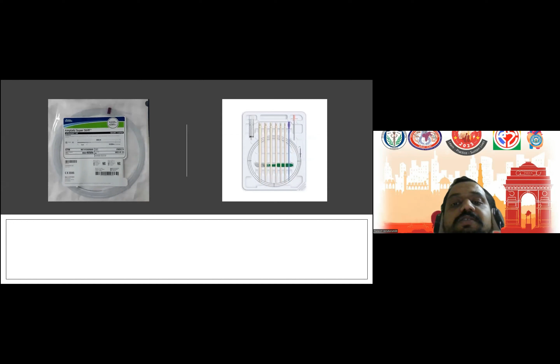Along with that, a multi-parameter monitor for the patient and one monitor for your circuit also, if you are measuring the pre-pump and the pre and post oxygenator P2 and P3 pressures. Because the machine does not have inbuilt P2 and P3 monitoring, you need an extra monitor for that. So these are the machines. Apart from the machines, let's see what stuff you require. One is your guide wires, and you need dilator sets of all sizes. Along with that, you need at least 6 clamps at the patient bedside. So just remember only one number in ECMO: whether you're cannulating, decannulating or changing any part of the circuit, you need to have at least 6 clamps.